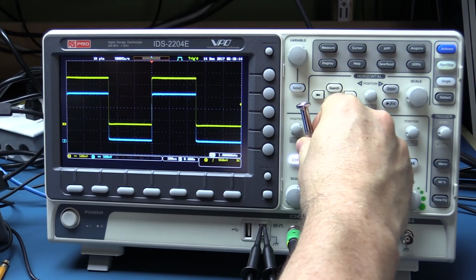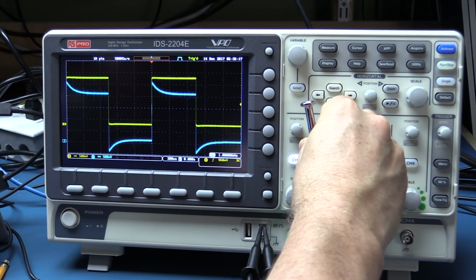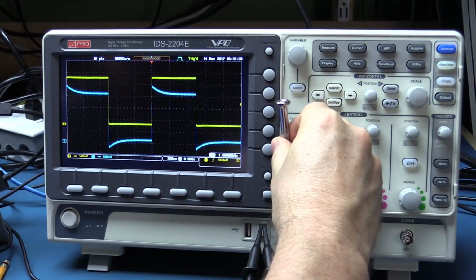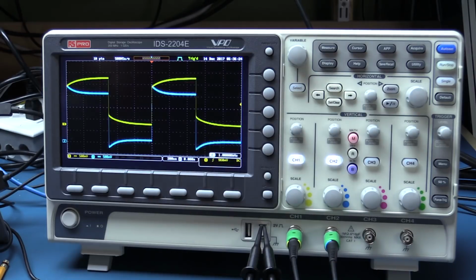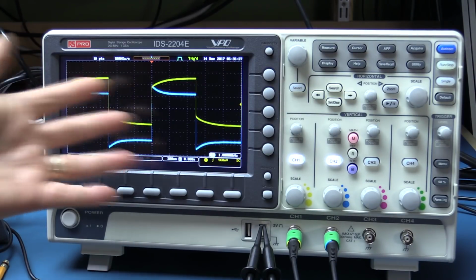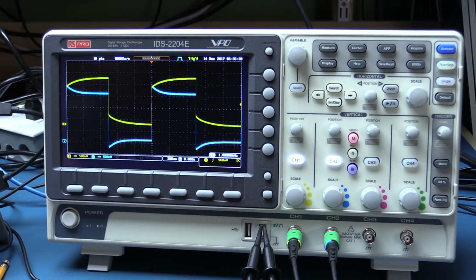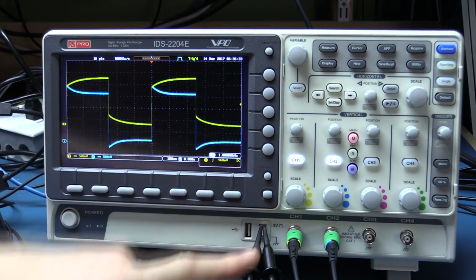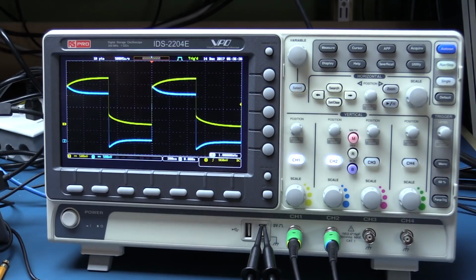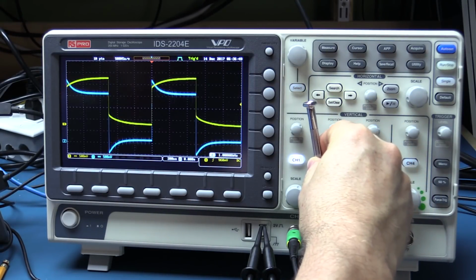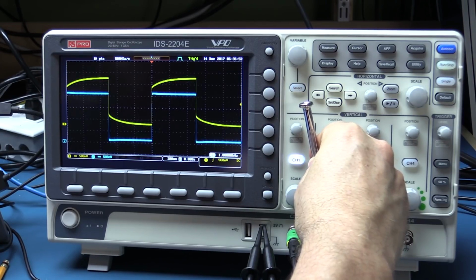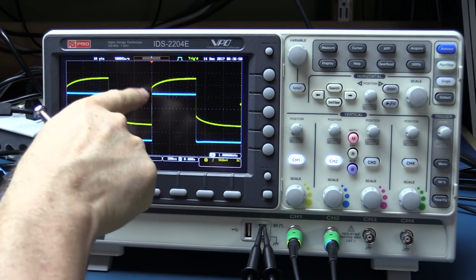so if on channel 2 I just tweak this around, you can see sometimes you'll get an oscilloscope and the probes, I'm going to do both of them, it doesn't take a moment to change it. All right, they could arrive at your door and you could see waveforms like this. This is completely incorrect, and all you have to do is clip it onto the probe compensation pin with the oscilloscope probe, and usually you do this in 10 times mode. These probes are fixed as 10 times probes, so you need to make sure that even in your oscilloscope setup you also set it to 10 times for the probes, and you just tweak the screwdriver to get them flat on the top and bottom and minimal overshoot on the leading edge and trailing edge.